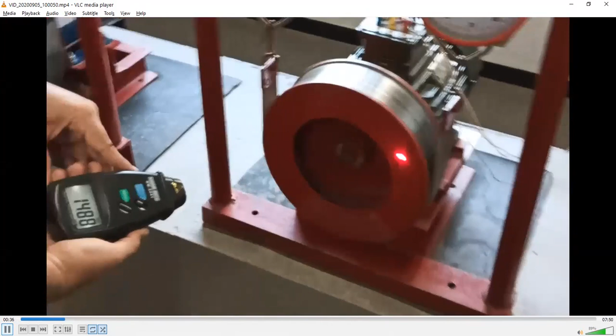So you can see that it's 5 kg load applied from the W1 and it's almost zero on the other. Please note down the scale of load applied, almost 5 kg, and let's observe the speed. So 5 kg from the W1, 0 from the W2, and let me also note down the speed. That is 1488. So let's note down the speed. It's 1488. Speed is around 1480.